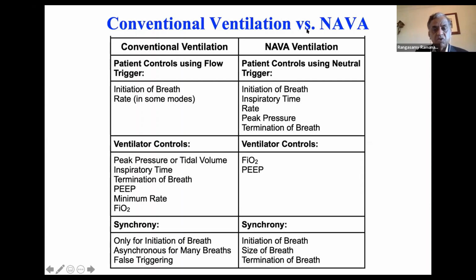The machine just supports it. What are the controls we use on a conventional ventilator? You all know that. You set a peak pressure; you set a tidal volume on a volume guarantee mode; you set an inspiratory time, you have to set termination of breath, and you have to set a rate in case the baby becomes apneic, and FiO2. On NAVA, the ventilator controls only the FiO2 and the PEEP. Everything else is controlled by the baby.